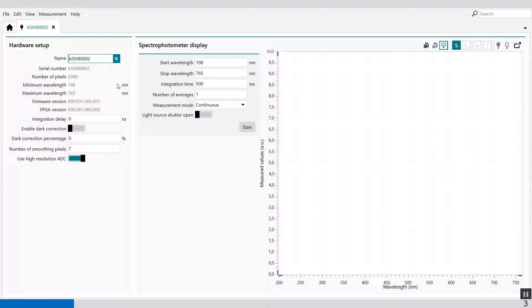The minimum wavelength is the lowest measurable wavelength of the detector, and the maximum wavelength is the highest measurable wavelength of the detector. The firmware version gives you information about the firmware used, and the FPGA version the same. These are all read-only parameters which cannot be changed by the user.